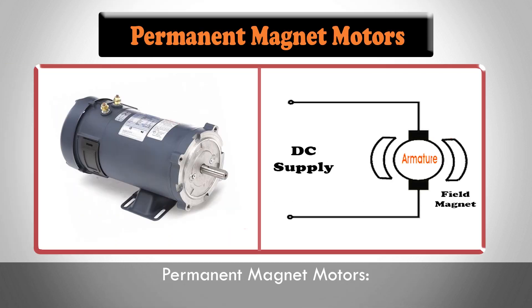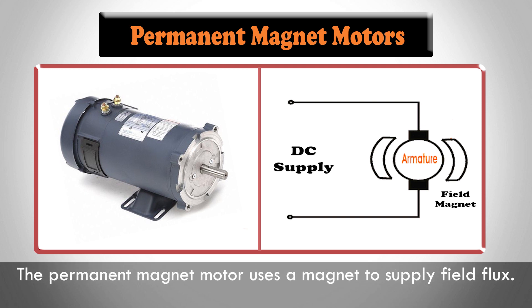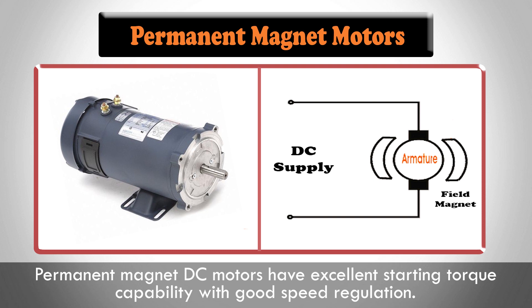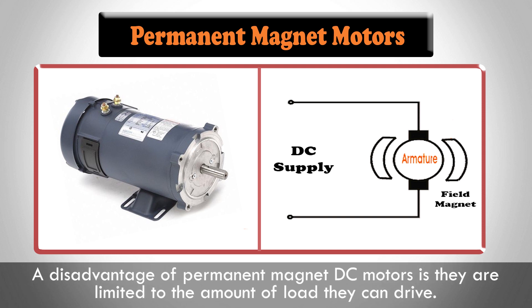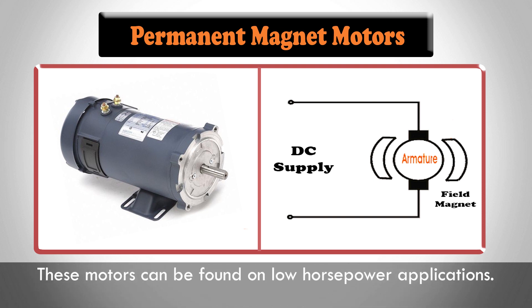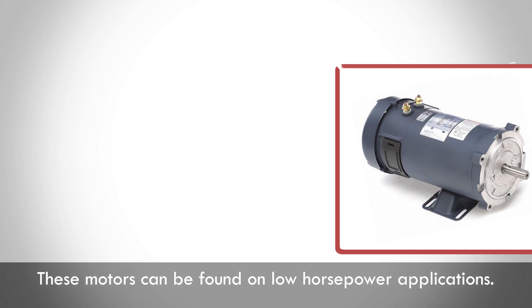Permanent magnet motors. The permanent magnet motor uses a magnet to supply field flux. Permanent magnet DC motors have excellent starting torque capability with good speed regulation. A disadvantage is that they are limited in the amount of load they can drive. These motors can be found in low horsepower applications.